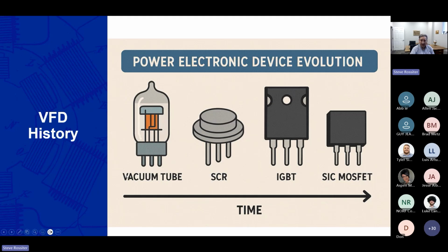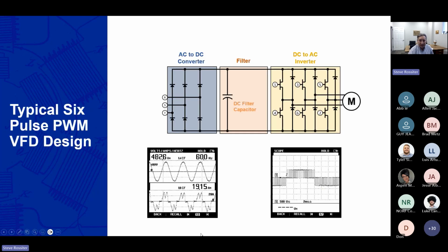As you look at that advent of the history from the vacuum tube all the way to silicon carbide devices, different challenges occur along the way. And that's where my career has kind of been developed in saying, okay, if we do one thing, what unintended consequence does that have? To get into exactly how these things work, and this might just be a little bit of a repeat for some of you, but a typical 6-pulse PWM drive, the kind that we have several thousand of in stock right now, from 1 horsepower to 800 horsepower in 230 and 460 volt, have a topology just like you see here, where there's a diode front-end bridge, a DC section with capacitor filtering, and an inverter section where you convert the DC to AC using that PWM.